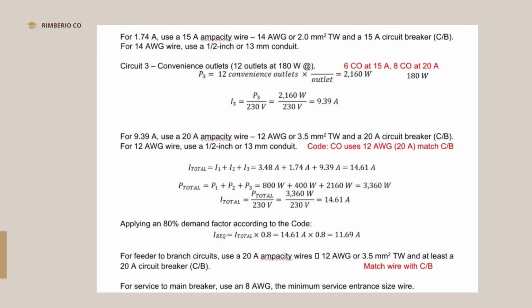Applying an 80% demand factor according to the code. So, I req is equal to I total times 0.8, which is equal to 14.61 amperes times 0.8, which is equal to 11.69 amperes. So, for feeder to branch circuits, use a 20A ampacity wire, 12 AWG or 3.5 mm squared TW, and at least a 20A circuit breaker. For service to main breaker, use an 8 AWG, the minimum service entrance size wire. So, yung 8 AWG na to, mas mataba, mas malaki na yung thickness niya.